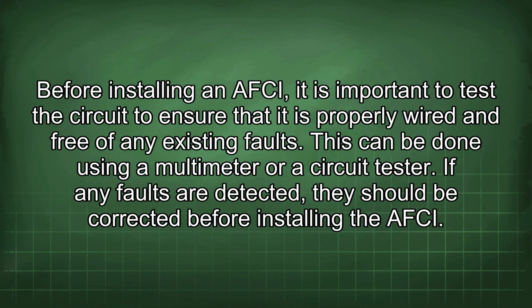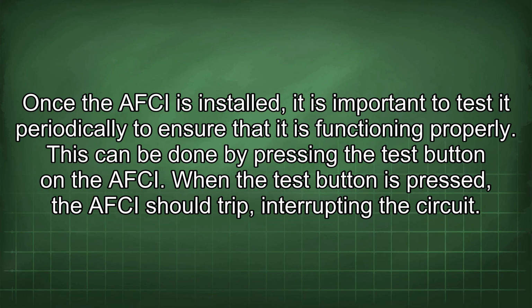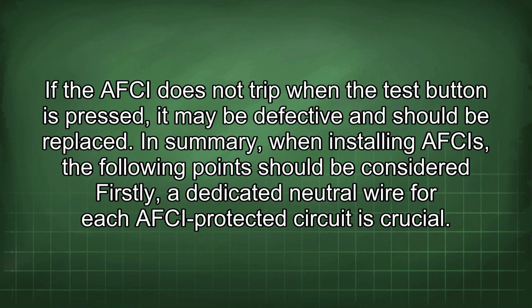Before installing an AFCI, it is important to test the circuit to ensure that it is properly wired and free of any existing faults. This can be done using a multimeter or a circuit tester. If any faults are detected, they should be corrected before installing the AFCI. Once the AFCI is installed, it is important to test it periodically to ensure that it is functioning properly. This can be done by pressing the test button on the AFCI. When the test button is pressed, the AFCI should trip, interrupting the circuit. If the AFCI does not trip when the test button is pressed, it may be defective and should be replaced.